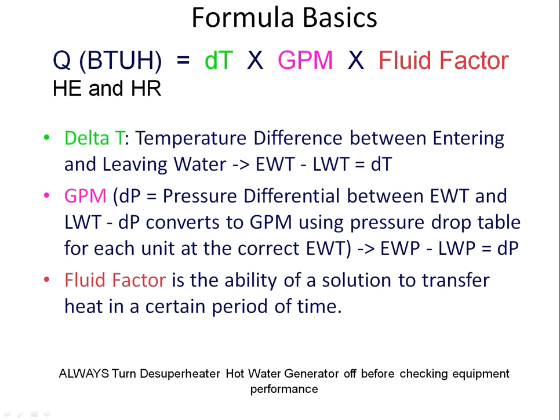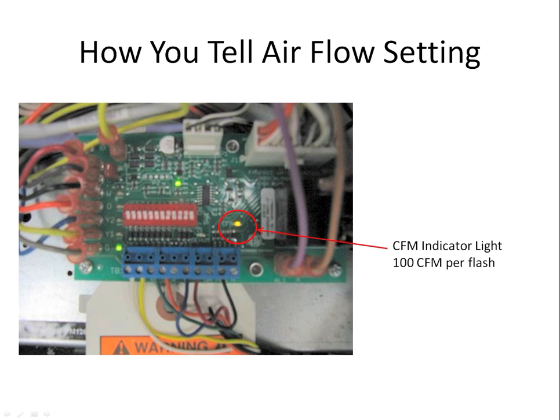I'm not going to cover all of this, but here's your basic formula for calculating your heat of rejection or heat of extraction. It's temperature difference, or delta T, times your flow rate, times your fluid factor. The fluid factor for water is 500. If it is other than water, it is 485. To determine gallons per minute, you have to convert from your pressure difference to gallons per minute. Again, we're not going to cover that at this point. We're going to reference that in the video, or reach out to your tech rep at your distributor level. They can show you how to do this. So that is your formula.